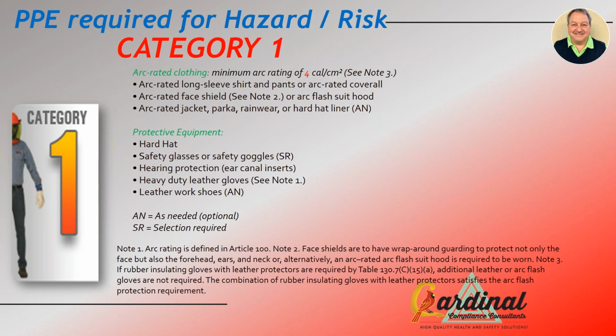Sorry, it took a second to get it up. That's now basically from an arc flash intensity of 1.2 calories up to 4 calories. It's now the bottom level of arc flash. And as we indicated, it implies that there is a sense of danger or hazard here, and you need to be protected. Now you can see there's more and more items that are required for your body or whatever is inside of this arc flash barrier to be protected. As we go up to Category 2, the level of protection goes up.